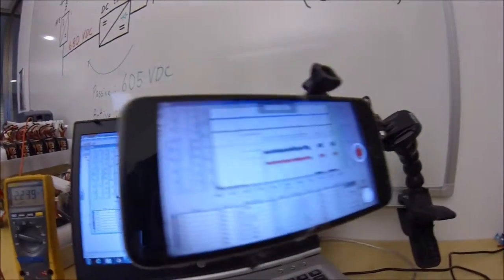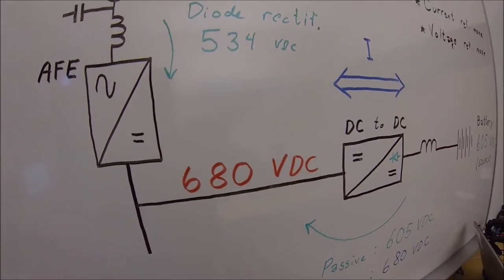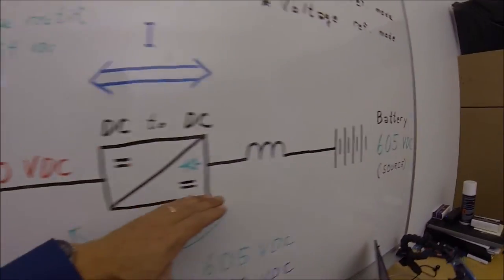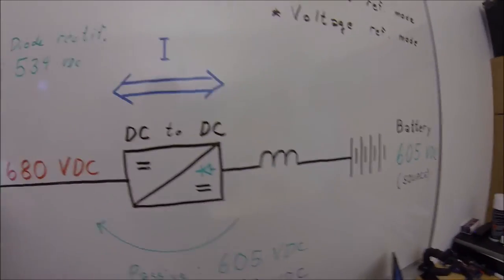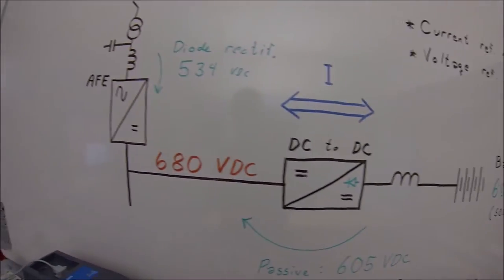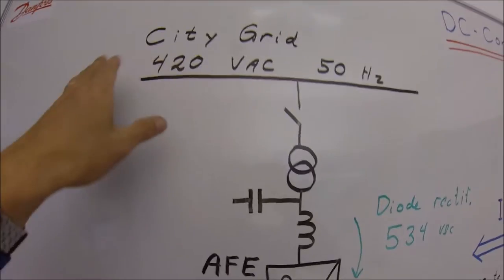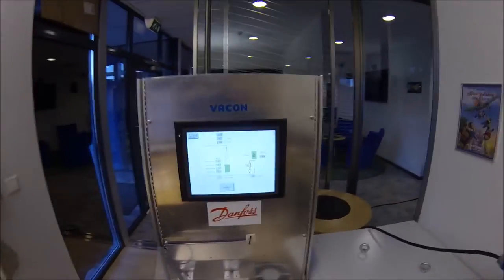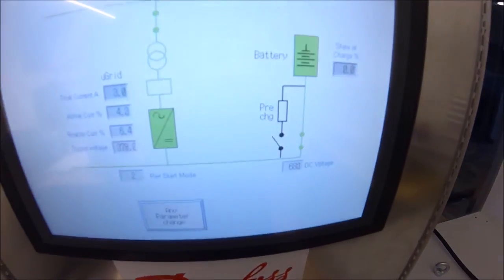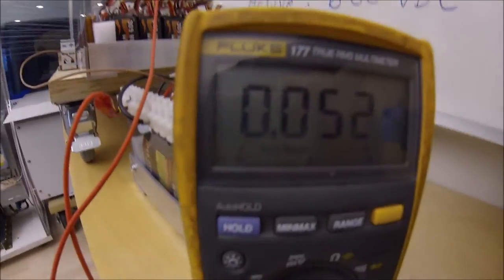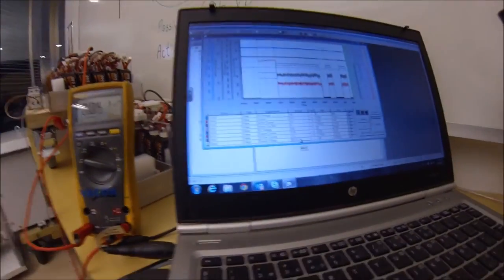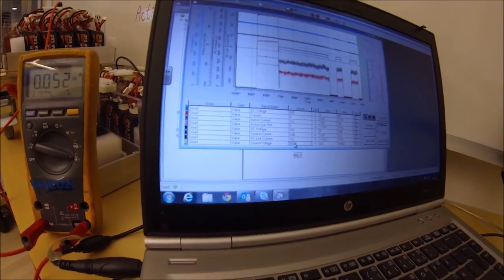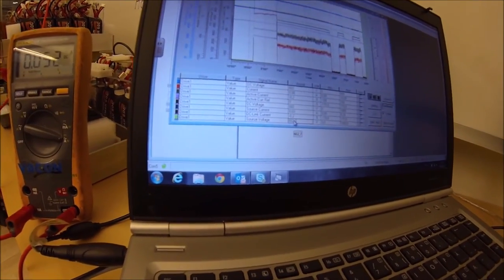Now that we are charging our battery in voltage reference mode, we will try to do something a little bit fun. And that is cutting off the common DC bus system while we are trying to achieve a higher voltage on the battery. We now have a current running into the battery for charging. And all the energy of course comes from the city, from the active front end. So if I disconnect the common DC bus, the 680 volt on the DC bus is not more available. And the current went down right now. What happened here? Well, the current went down to zero because there is no energy source anymore. We also see that our source voltage, that is the battery voltage, went down quite a bit.